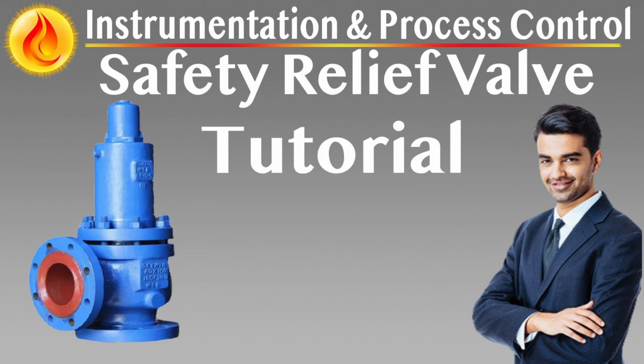Redundancy and reliability measures. Consider dual pilots or instrumentation alarms on sensing line blockage or temperature drops in critical services. Ensure testing and commissioning routines validate pilot opening under simulated process conditions. Some PORVs include internal heaters or traceable housings to mitigate freezing risks.